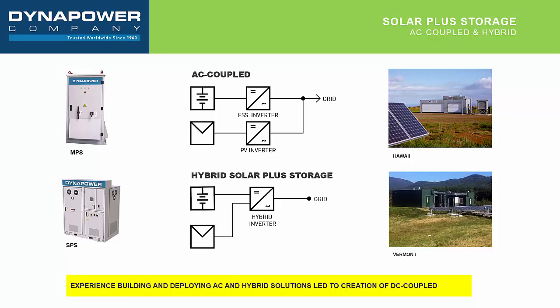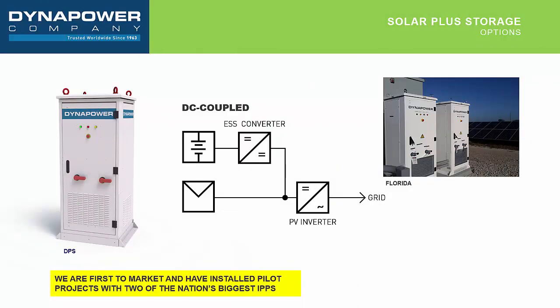So then the question is, how can you capture the value and the benefit of DC coupling, electrically speaking, and yet at the same time have the flexibility that you would normally see with an AC coupled array? The answer is that you can take that DC-DC converter, which previously was inside the hybrid inverter, take it out of the hybrid inverter, and create a separate dedicated DC-DC converter, as depicted in this slide. This DC-DC converter can then be parked behind the PV inverter on the PV bus. The simple diagram here shows a single unit, but you could have multiple DC-DC converters tied into that DC bus. So you get all the advantages, which we'll talk about with regard to DC coupling, without the limitation that you have with a hybrid inverter on the sizing flexibility.